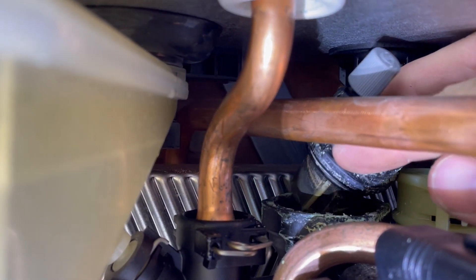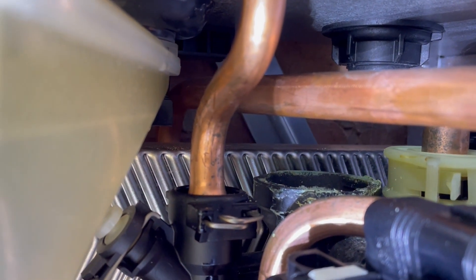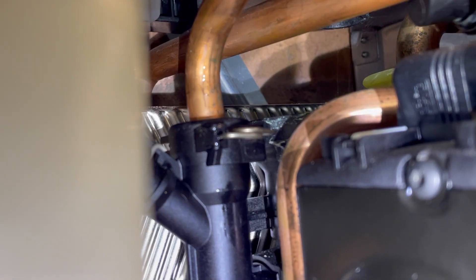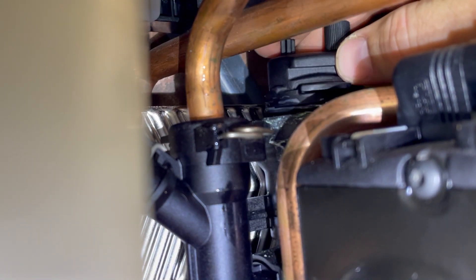Once you've removed the old air vent, make sure that you get the washer with it — a little rubber ring washer. That's always nine out of ten still in there. Clean up the housing because debris can build up. Once you put the new stuff in, it might potentially leak. Lube the new one up before you put it in, then press down and twist in the opposite direction.